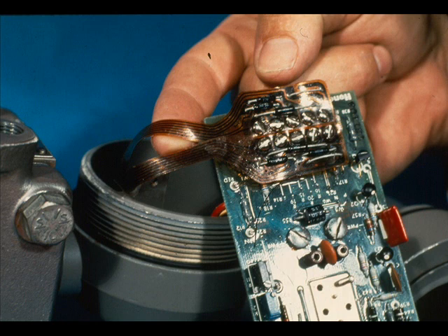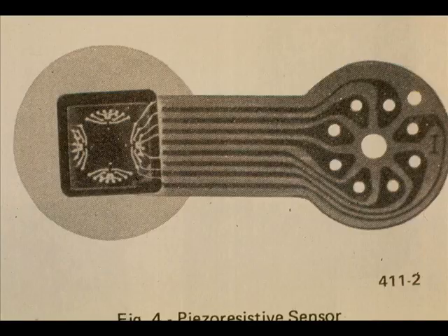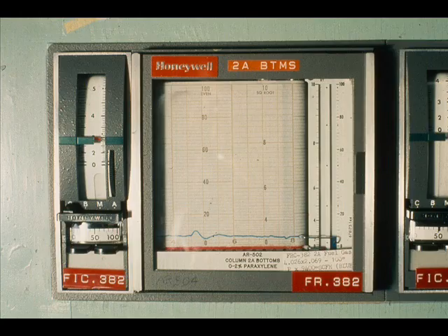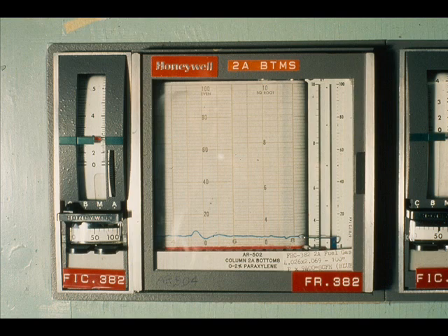The circuit board furnishes a constant current to the strain gauge bridge circuit and receives a signal from the sensor that it converts to the 4 to 20 milliamp DC transmission signal for the receivers in the transmitter loop.